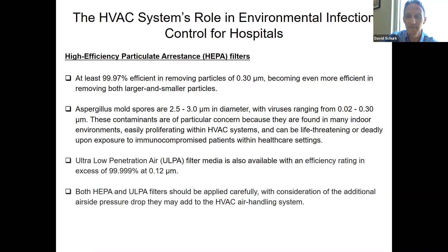Now there are caveats to that. It's not as simple as pulling one filter out and putting a higher efficiency filter in. You have to look at some things first, because for every action there's an equal and opposite reaction. It can create more resistance, airflow might drop, you bring in less outdoor air, and have fewer air exchanges, which can negatively impact the environment. So I offset my good deed with an implication on the other side. We need to take all of this into consideration when making these changes, but it's definitely worth considering and can be very cost effective if done right.